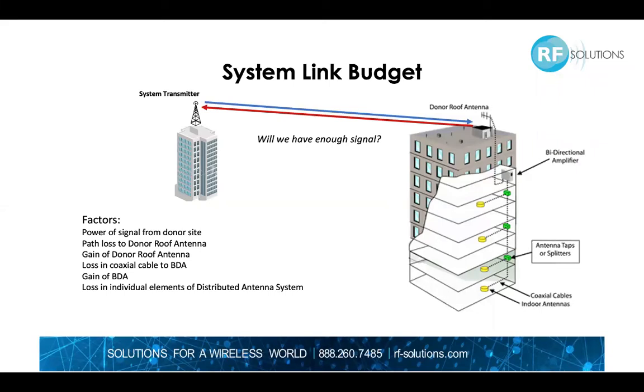After the installation has been completed, actual signal levels are measured at the BDA for confirmation. The gain of the BDA is adjusted to provide necessary signal levels to each of the antennas, overcoming loss in the cable runs and antenna taps or splitters.